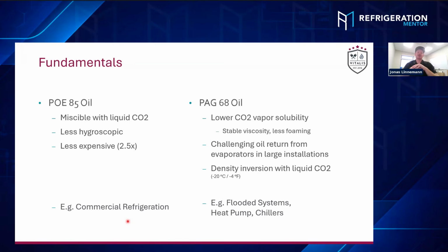And also if you have flooded systems, because that's what PAG oil is many times used for, CO2 flooded systems, heat pumps because of the good viscosity properties, or chillers. In these systems, you have this density inversion point with the liquid CO2. That's quite interesting because the oil is typically sinking to the bottom of the liquid phase, like in ammonia systems. But as soon as you go lower in the saturation temperature of the liquid CO2, it basically starts to swim. So there's more or less an application limit. If you go too low, you can't separate the oil anymore.